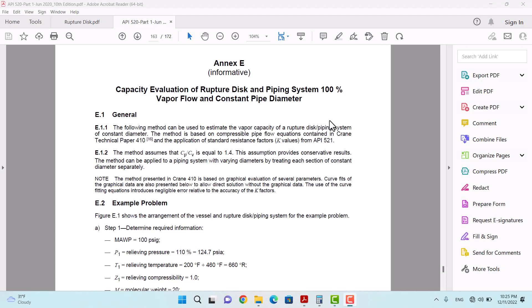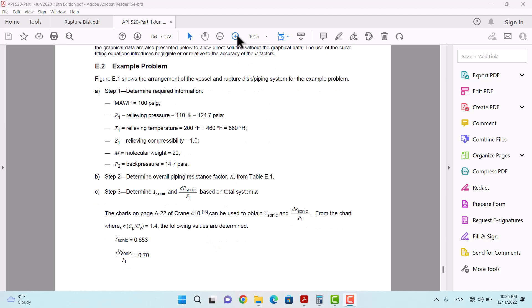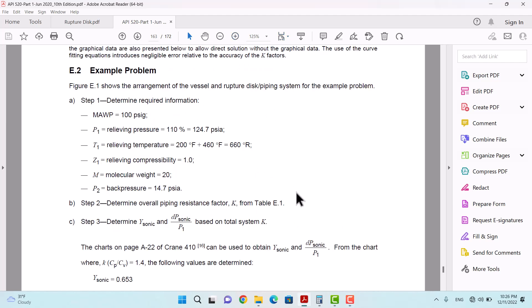In these episodes, as I promised, this is the following episode of the first episode about the general guidelines toward the design of rupture disks. Specific examples from API Annex E are described, and you are going to see how this rupture disk is going to be sized for a real case problem. If you go to the Annex E of API 520 Part 1, and look at the capacity evaluation of rupture disk and piping system — vapor flow and constant pipe diameter — here is the example problem. This is a very good example, and I really wanted to share it to better understand the sizing procedure for rupture disks using the example provided by the API.